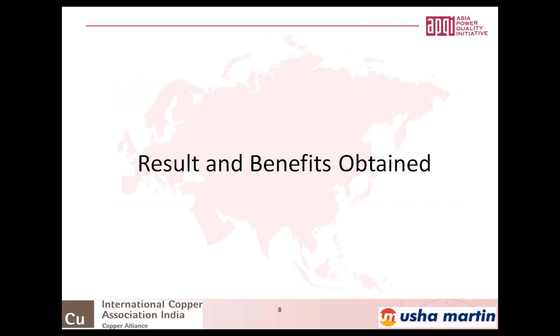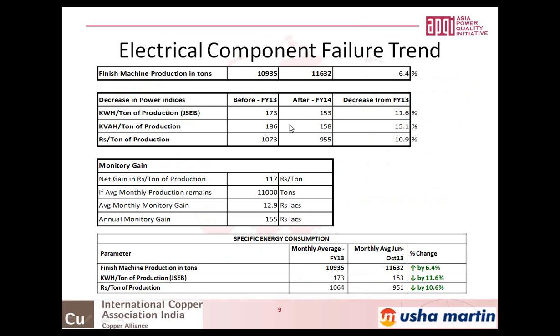After installation of the harmonic filters, I just want to share the benefits of these filters. You can see the power consumption was reduced from 173 kWh per ton to 153. There was a reduction of 20 kWh per ton, a reduction of 11%. Similarly, there was a reduction in rupees per ton also. We got the benefit of reduction in power consumption, which was also around 10.9%.